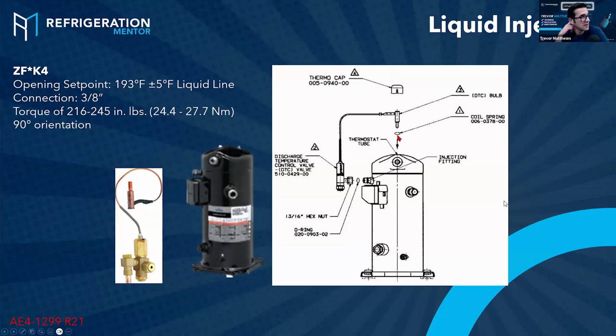I had a guy from down in Dominican, I think, maybe Turks and Caicos. He reached out to me and they were having problems. It was tripping off. And I asked him all the questions. He said, oh, it's all set up. But because his technician told him it was all set up, he actually went out to the site and pulled it out, and there was no spring there, and it was tripping off on a high head. It wasn't getting the cut. So that holds it in there nice and tight. And you have to put thermal paste in there as well.